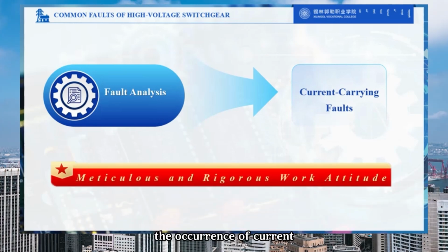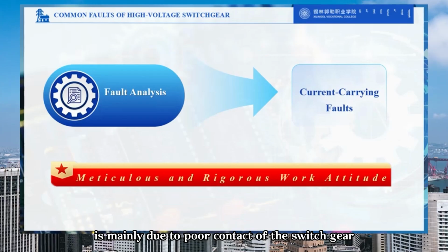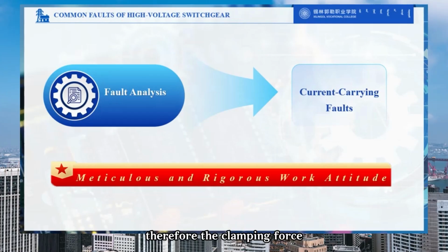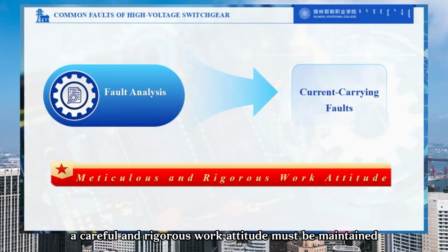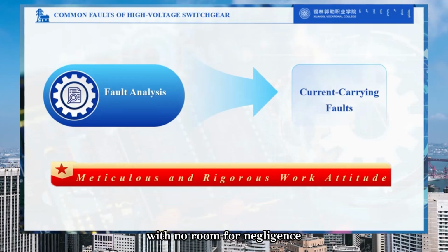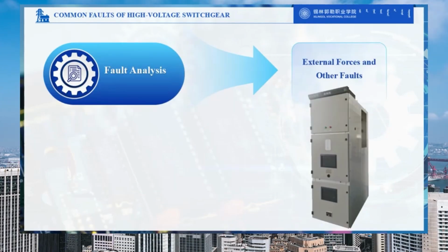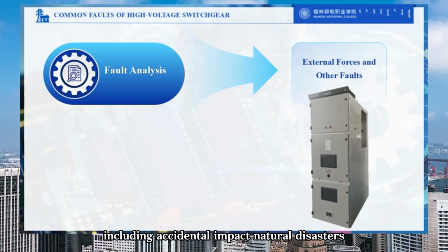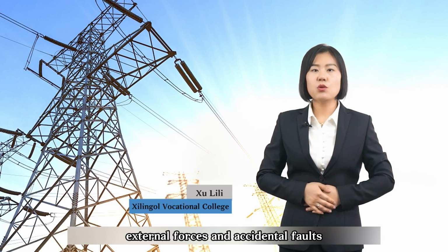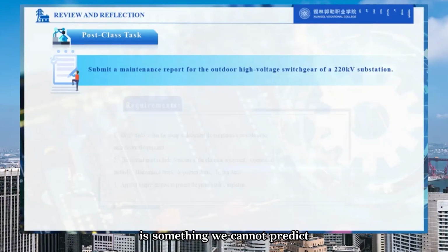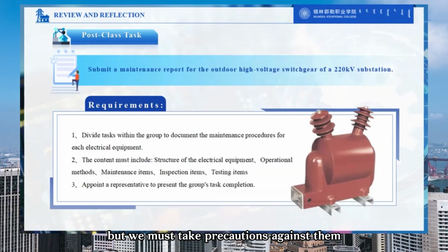Another common fault is current carrying failure. The occurrence of current carrying failure is mainly due to poor contact of the switchgear isolation plugs, leading to contact melting. Therefore, the clamping force and tightness of the plugs and contacts are very important. During selection and inspection, a careful and rigorous work attitude must be maintained, with no room for negligence. The last type of fault involves external forces and other faults, including accidental impact, natural disasters, short circuits caused by small animals, etc. The occurrence of other unknown external forces and accidental faults is something we cannot predict, but we must take precautions against them.